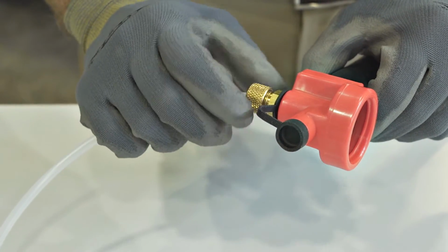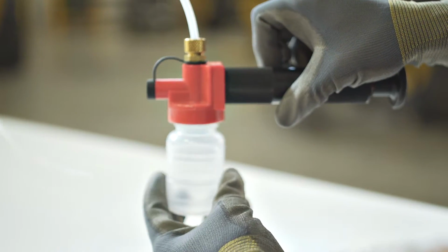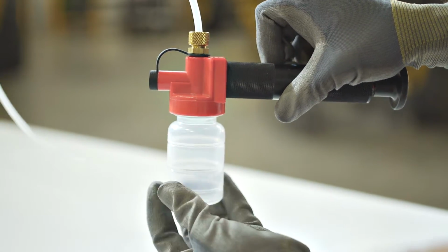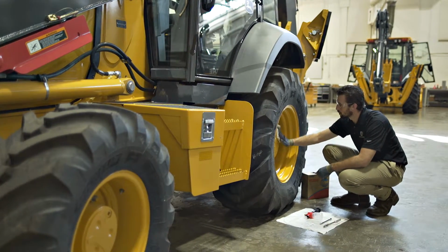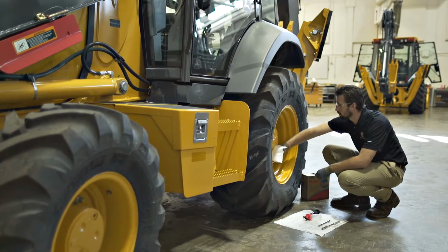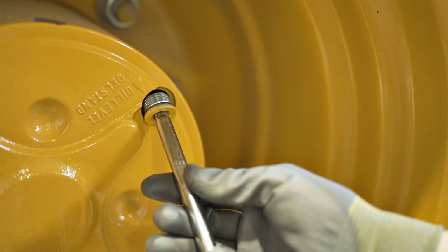Insert the tubing through the head of the vacuum pump and tighten the retaining nut. The tubing should extend about 1/8 of an inch beyond the base of the vacuum pump head. Clean the area before opening the reservoir access. Sample from the inlet side of the reservoir if possible, and always sample from the same fluid level.